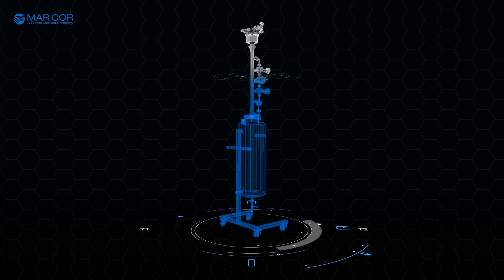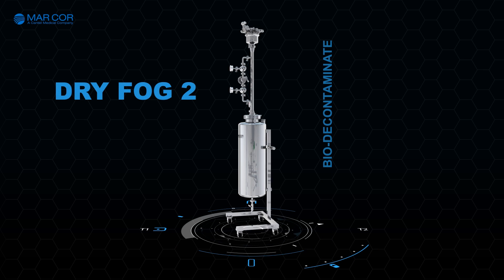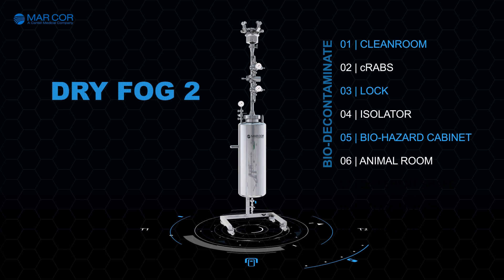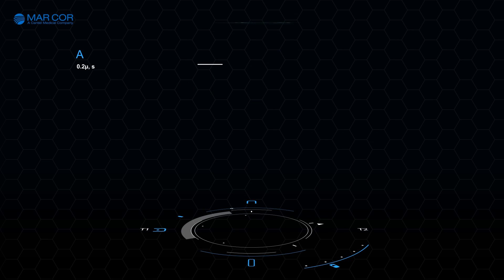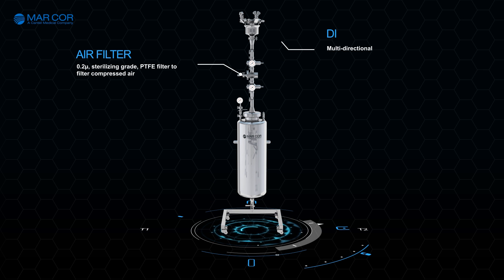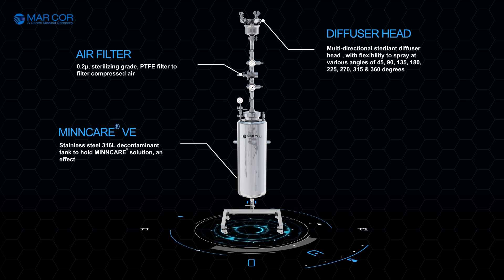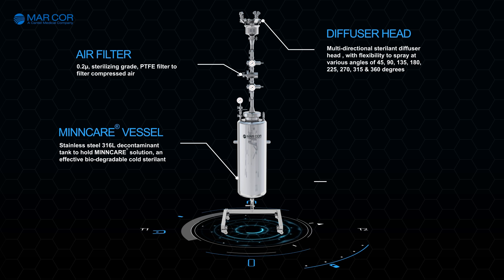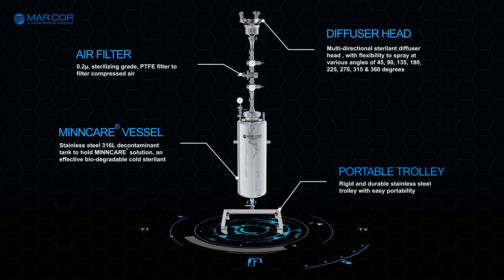The Dry Fog technology is used to effectively bio decontaminate clean rooms, C-RABs, locks, isolators, biohazard cabinets and animal rooms. Dry Fog 2 consists of a 0.2 micron hydrophobic PTFE sterilizing grade air filter to filter compressed air, a multi-directional sterilant diffuser head to spray at various angles, a stainless steel 316L decontaminant tank to hold the Minncare solution, and a rigid and portable stainless steel trolley for easy portability.